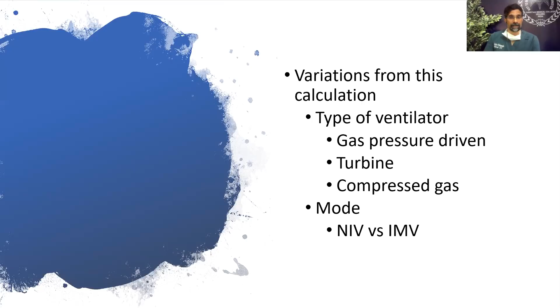So now that we've looked at how much oxygen is consumed by the ventilator, what can we do to reduce the oxygen consumption? What can we do in terms of ventilator settings? The first thing to remember is that invasive ventilation by itself actually saves oxygen. In this patient scenario, it was about 10 liters. Most patients would consume about 15 or 20 liters per minute at the maximum. Other methods of ventilation like NIV or even high flow or even certain grades of Venturi devices use much more oxygen than that. So invasive ventilation typically uses less oxygen than other types.